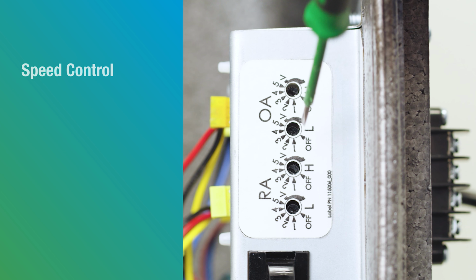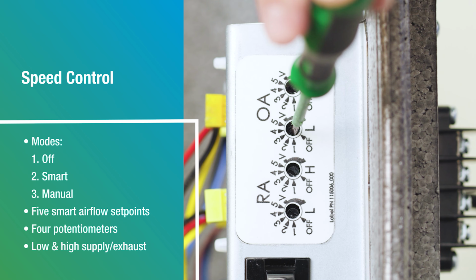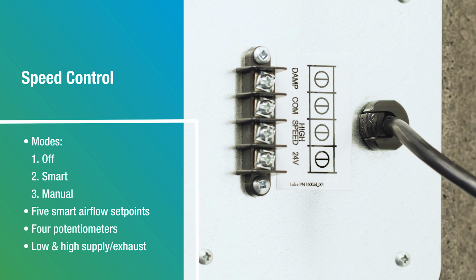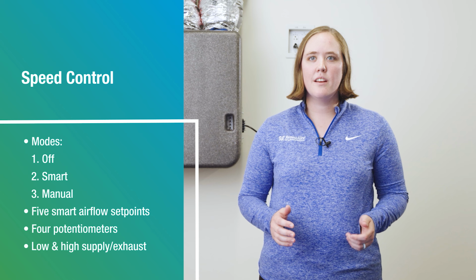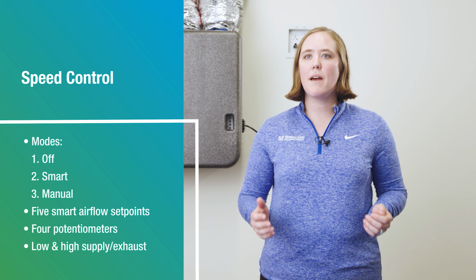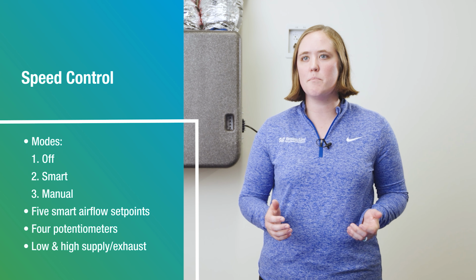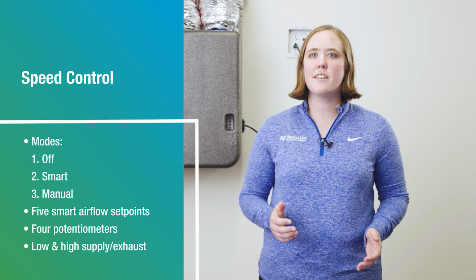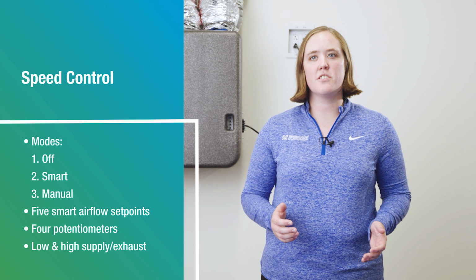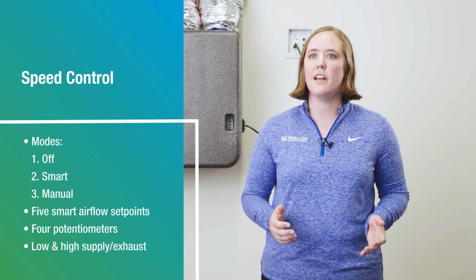The unit's speed control has 4 potentiometers to independently set the low and high speed settings for both the supply and exhaust airflows. Each speed setting has 3 modes: off, smart constant volume, and manual. There are 5 smart constant volume airflows. These selectable airflows will automatically adjust the EC motorized impellers to keep the unit running at the selected airflow, even as filters start clogging or duct pressures fluctuate with the cycling of a central air handling unit.